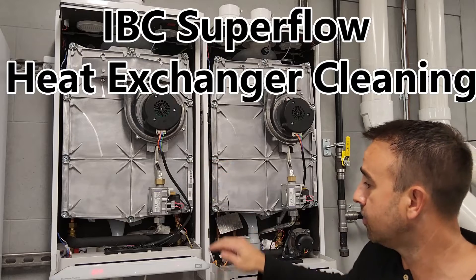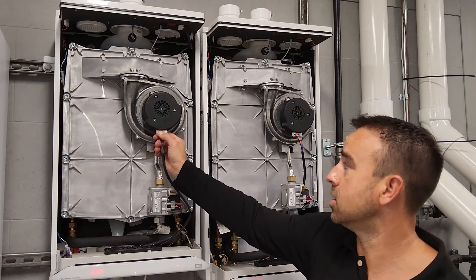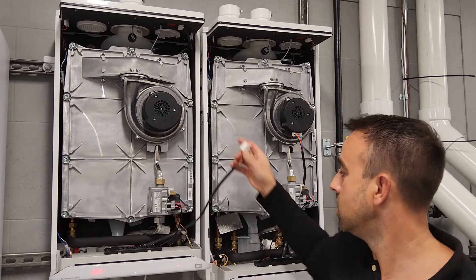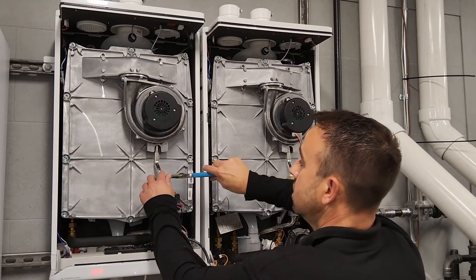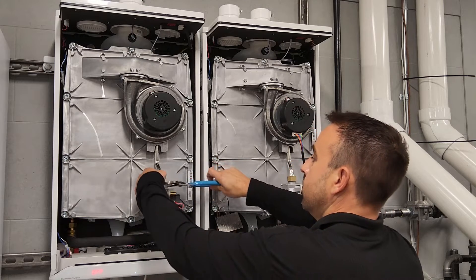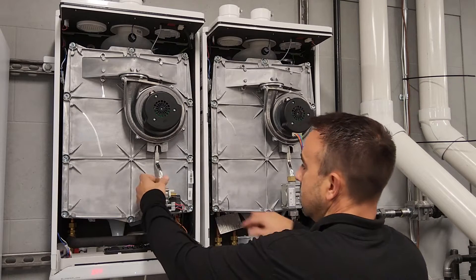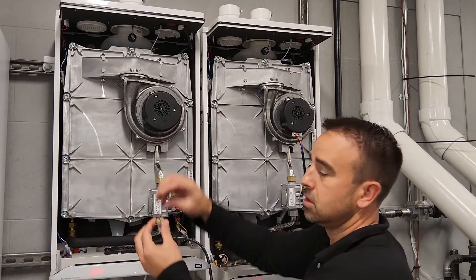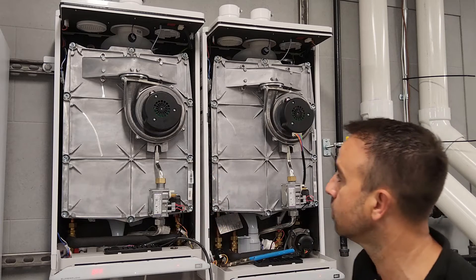So first off, units off. I'm going to actually remove this Molex connector and it comes right down. Just pull that away. Next I have my channel lock and I'm actually going to loosen this nut on top of the gas valve. Underneath that should be our orifice — so you've got a natural gas or propane orifice. Make sure you capture that, don't lose it.